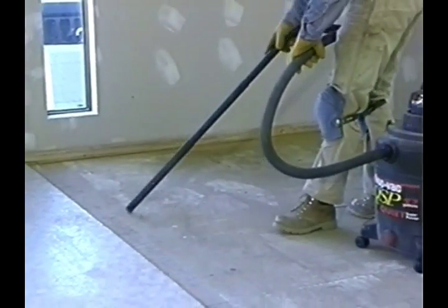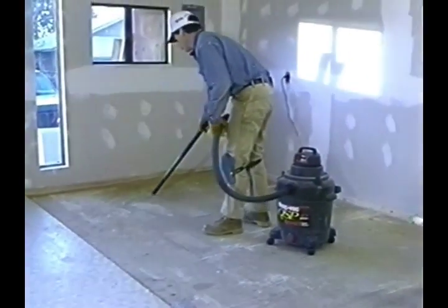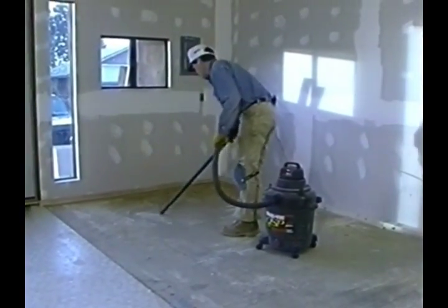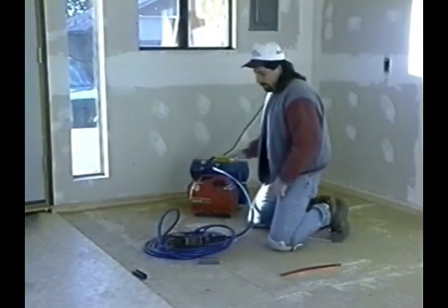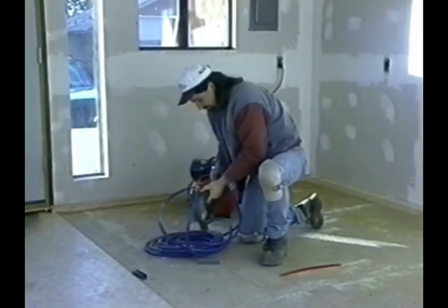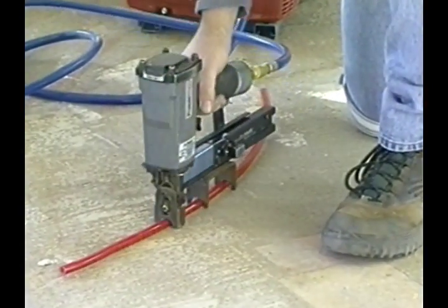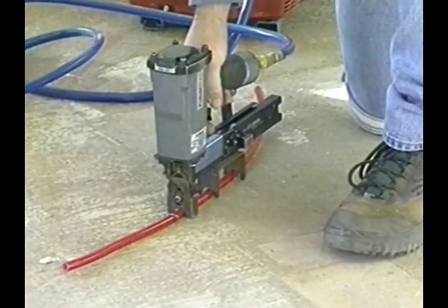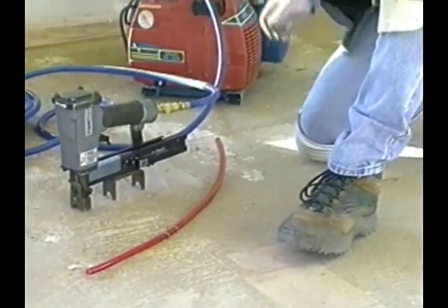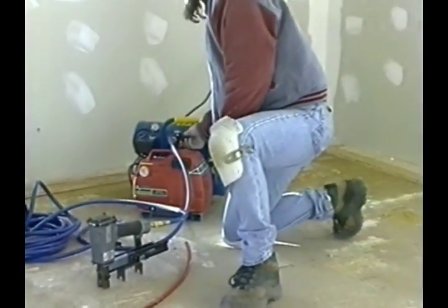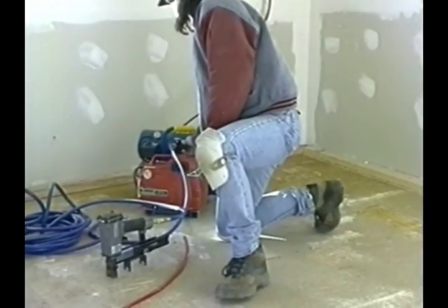It's essential to begin a Stapledown project with a clean working area. All debris should be removed from the area where the tubing is to be located. Before you begin stapling, you should set the pressure of your staple gun. This project will use a pneumatic staple gun. Using a scrap piece of tube, set the gun around 40 pounds of pressure and staple the tube. The staple should hold down the tubing but not kink it.